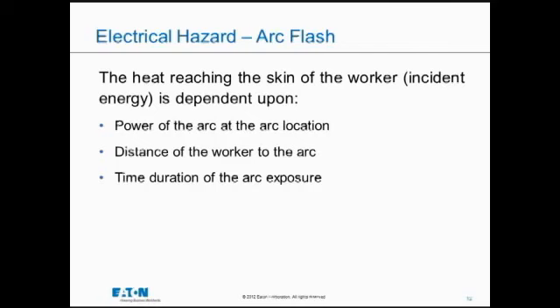What's coming at us from an arc in terms of heat energy is dependent on 3 things. How powerful is the arc? And power in the electrical world is voltage times current, volts times amps, at the arc location. How close is the worker to the action where the arc's occurring? That's worker distance, and we can work on that one later on in this presentation. And the last one is how long is the exposure? A brief exposure may not be as bad as a long duration exposure. And certainly in the calculation standards, they talk about a person jumping out of the way in 2 seconds. Whether or not that could be done is sort of a judgment call, but we use time in that fashion. So it's power, distance, and time that are the big components of arc flash calculations.